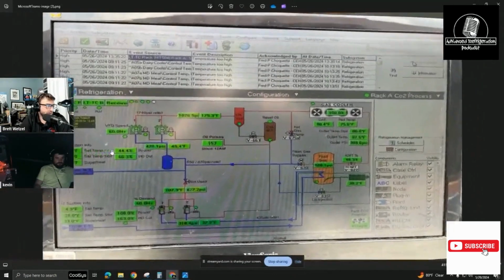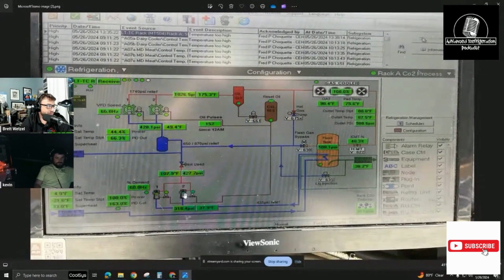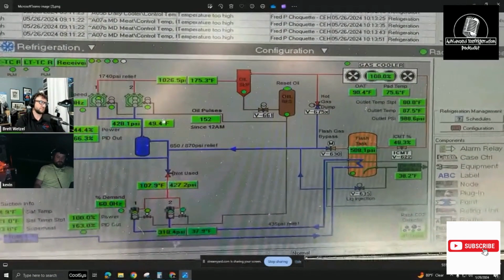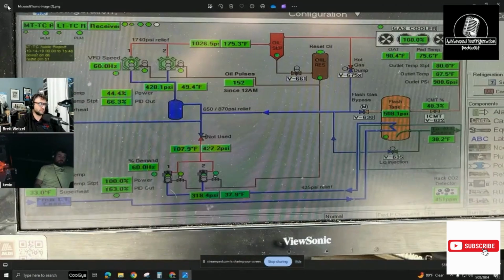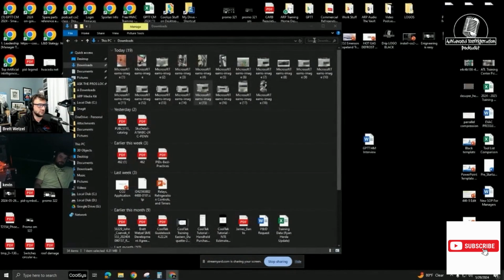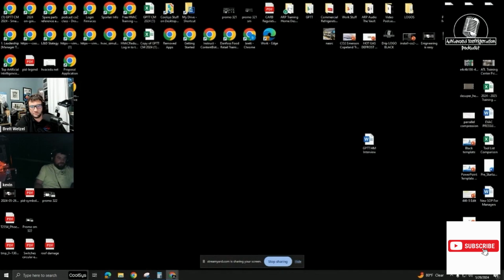The only thing that was hokey was the oil pull. That was fine. The temperature right then was fine. But at one point, as soon as you lost that one low temp compressor, forget it. It didn't like it at all. Yeah, that is a huge problem with them. Once it loses that low temp compressor, it's done. And if you have pieces of rubber in your rack, you're pretty much done too.